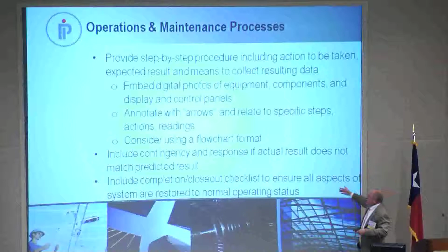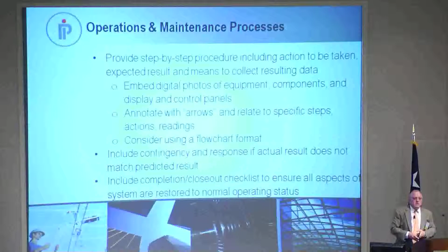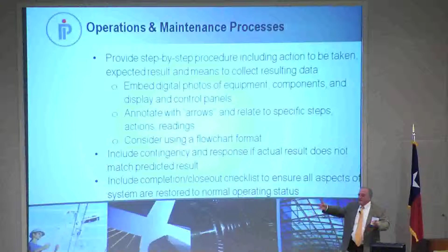This is one that seems to bite even our smartest clients. You've got to make sure that after you do a work routine, you restore the systems to normal operating status. We've had calls where people said, hey, I had a utility outage and my generators didn't start. You go to the site and find out they did an oil change on all the engines and left all the engines in manual. They didn't go back and restore the system to normal operating status, and that failure caused a major outage.